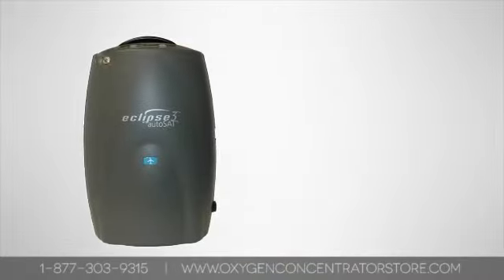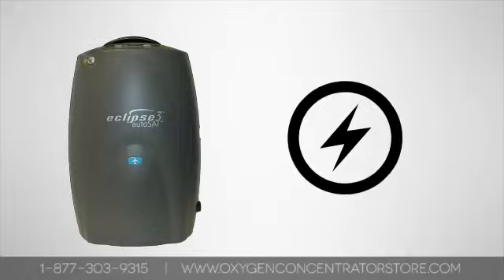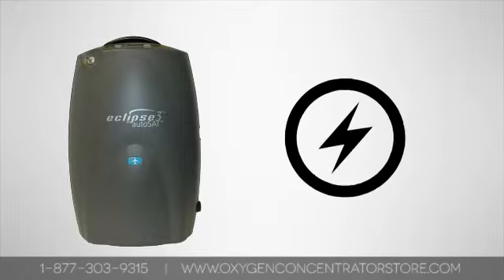One portable oxygen concentrator, the Sequal Eclipse III, requires that you remove the battery from the unit while operating it in the car. By leaving the battery in the unit, you can draw too much on the vehicle's own battery. This will result in a depleted car battery.